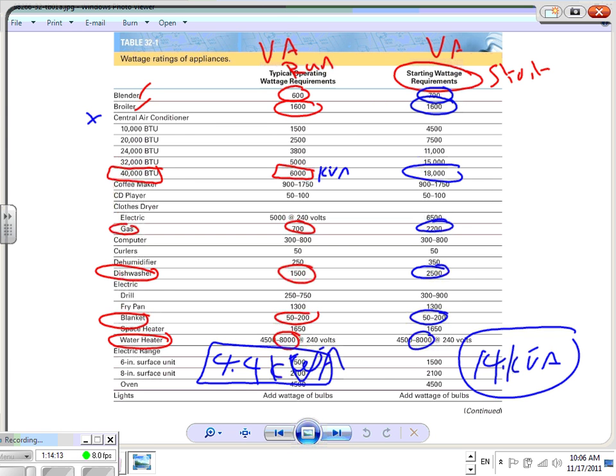You have to size a generator based on two things. Please remember this for the software that is coming next quarter. Help me or help you. Because the software that we have is going to ask you, when you plug in these numbers, for two numbers for every load. It will ask what's the horsepower of this equipment? Here's horsepower, 515 horsepower. What's the starting of this equipment? If you don't know, it allows you to pick the code letter for the equipment, and based on the code letter from the NEC code book, it will assign a starting kVA for it. So the software is really easy because it walks you through the start kVA.